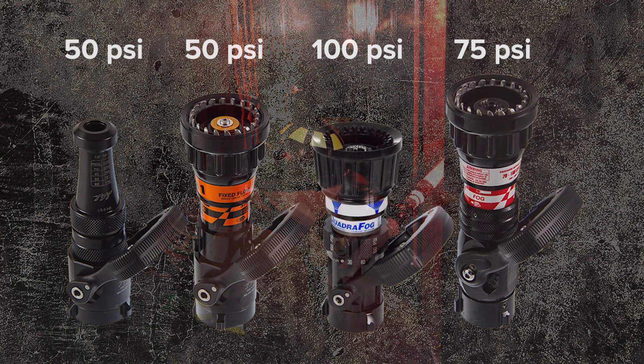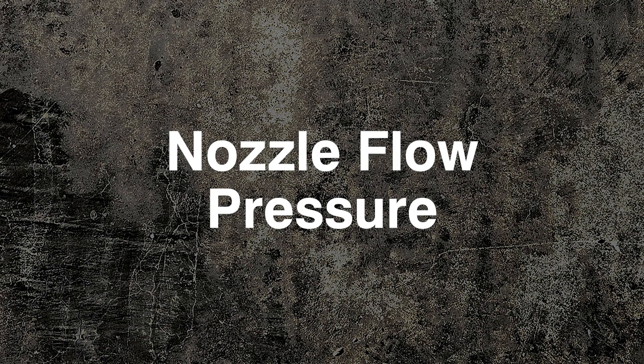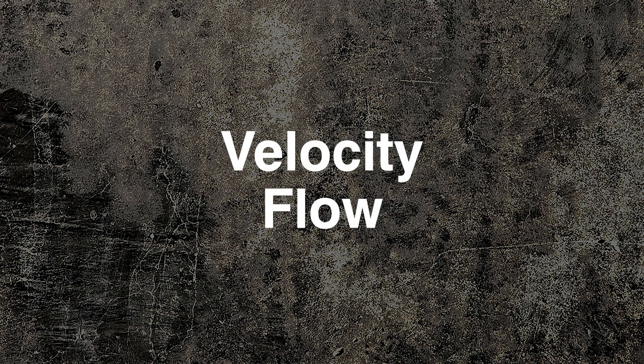Nozzle flow pressure is the discharge pressure of a firefighting nozzle at a given flow rate. Nozzle flow pressure is also a direct indication of the velocity flow for a fire stream in feet per second.